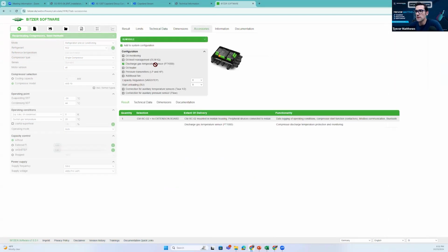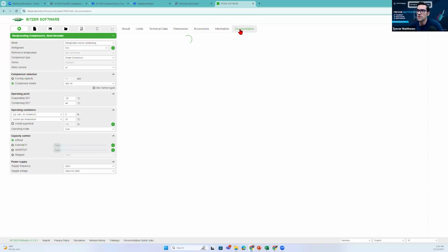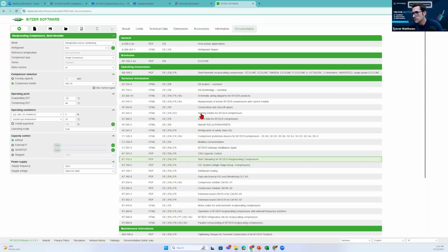So what do we need? We need a discharge temperature probe. And right here it says this module, let's say, doesn't even have refrigerant injection on this one. So this compressor can go without refrigerant injection. You just need an additional fan for this compressor. That is impressive. Sometimes there's a water-cooled head. And so when you get in here, here's where all the different information is.